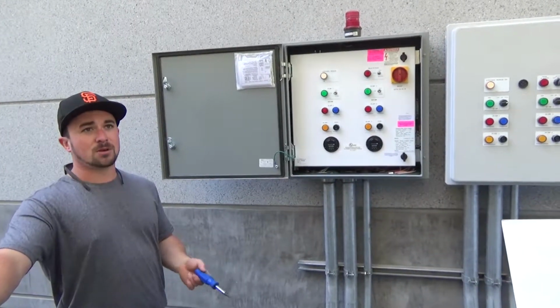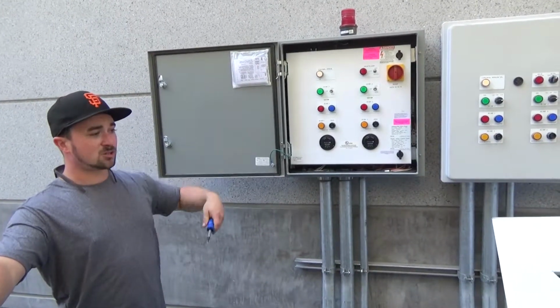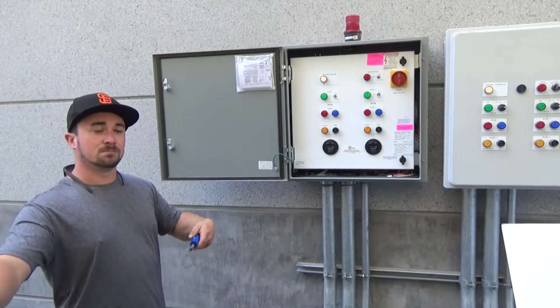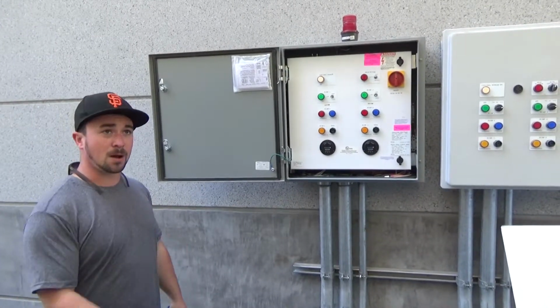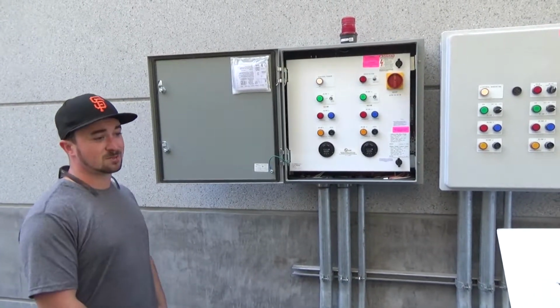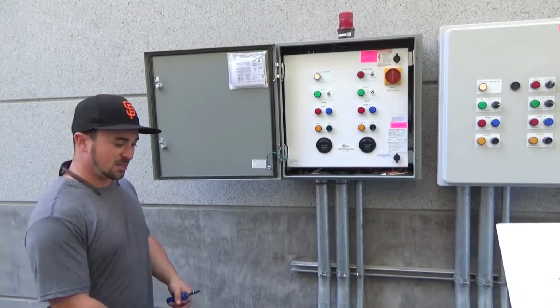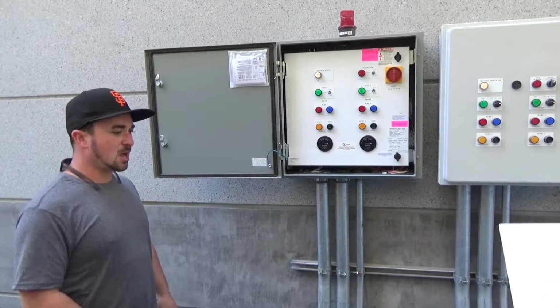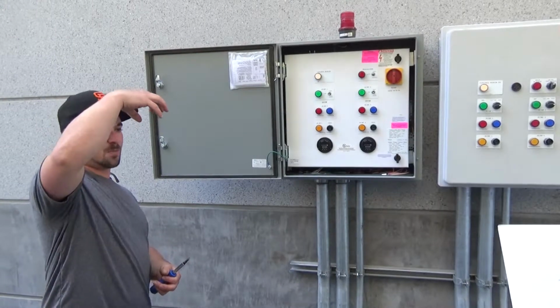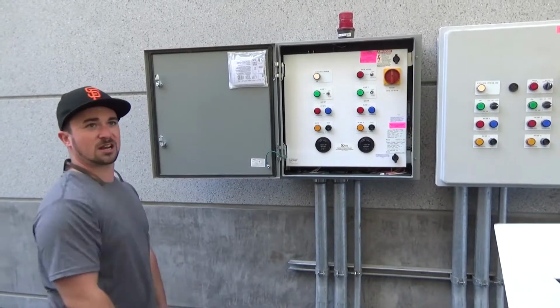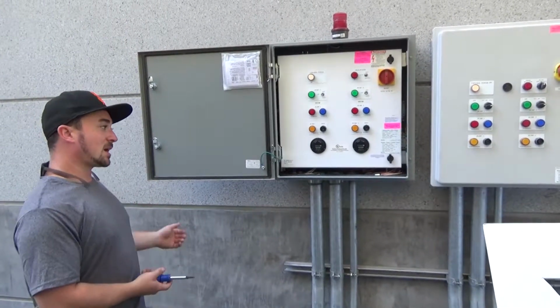Sometimes it doesn't come out, and what happens is if you pump it down too far, they'll have trouble. Once the pit fills up again, they'll have trouble pumping out. You'll have to sometimes turn them on and then throttle the discharge valve a couple times, or bring them out, turn them on, and then put them in the water while they're running to try to get that air kicked out. It's kind of a pain sometimes.